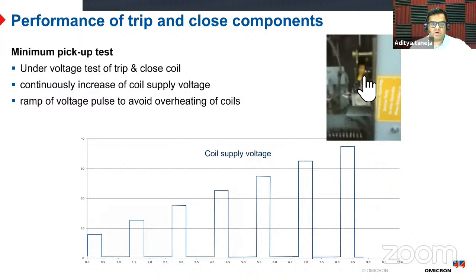So at some point, finally it operated, and then that's where it stops. So we get to a point where we get the voltage, and this voltage should normally be less than 60%. That's a general recommendation from my side. Normally people accept 70% also, but that's okay. But 60% is good, because these things are not so expensive compared to the breaker, or the kind of expenses that you would need to incur in case it does not operate, which are huge. So 60% is a good number to be safe.